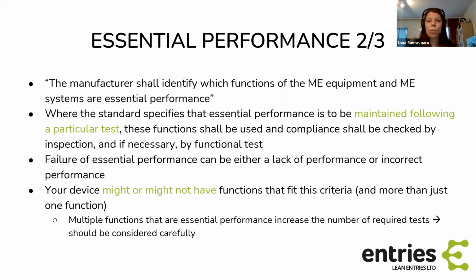So it's maybe not just one, but because there are those tests that were mentioned that say that essential performance is to be maintained following a particular test, then do note that if you have multiple functions that you defined as essential performance, you will have to do these tests that many times. So it increases the complexity of testing quite a lot. So do consider carefully whether this is essential performance or not. If you have, for example, identified that you have 5 functions that fit this criteria, then perhaps consider this again. But that is, of course, possible depending on how high risk class your device has as well.